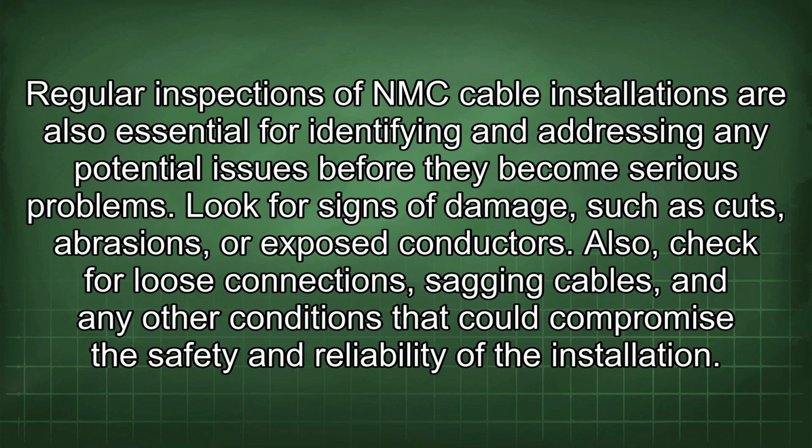Regular inspections of NMC cable installations are also essential for identifying and addressing any potential issues before they become serious problems. Look for signs of damage, such as cuts, abrasions, or exposed conductors.